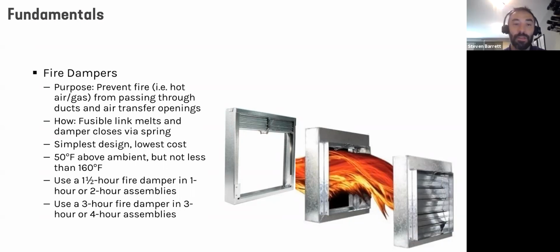Fire dampers come in 2 flavors, hour and a half, 90 minutes, or 3 hours, 180 minutes. Anytime you're penetrating a 1 or 2 hour assembly, specify a 90 minute or 1.5 hour damper, and then use 3 hour dampers for 3 or 4 hour rated assemblies. These could have an electronic type of actuator, but typically it's a fusible link. That's why these are the cheapest and easiest to install.